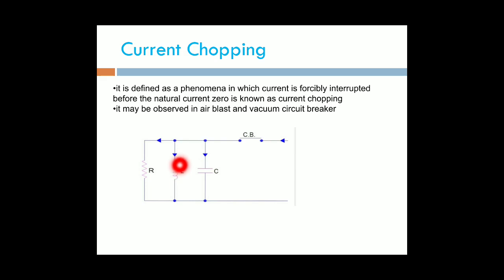The current flowing through this reactor is I, and hence the stored magnetic energy in it is Li square by 2. But as soon as the breaker contacts open, current chopping will take place. Current chopping means that before the natural current zero, the current is forcibly interrupted. In this condition, the current through the reactor becomes 0.